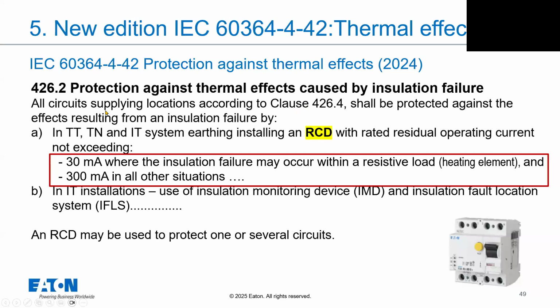Then look especially to this paragraph, 426-2, protection against thermal effects caused by insulation failure. Here it's mainly focused on RCDs. There is description for the case RCD is used in TT, TN, or IT systems. They must generally be 300 milliamps or so.